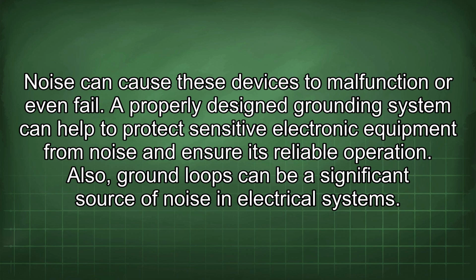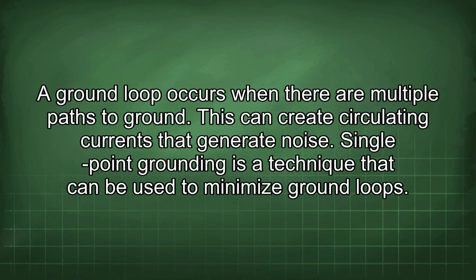Also, ground loops can be a significant source of noise in electrical systems. A ground loop occurs when there are multiple paths to ground. This can create circulating currents that generate noise. Single-point grounding is a technique that can be used to minimize ground loops.